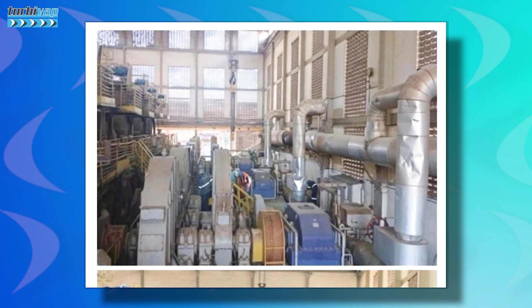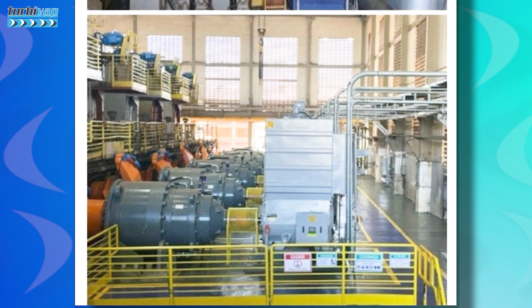Although robust and being improved to optimize their efficiencies, turbines face increasing challenges, such as stricter environmental regulations, carbon taxes, increased operating costs, and the need for greater availability and efficiency. When these machines age or no longer meet modern demands, replacing them with electrical systems appears as a strategic solution. Why this pressure for change? First, emissions. A simple gas turbine emits about half a kilo of CO2 per kilowatt hour, which for an 8 megawatt compressor operating 8,000 hours per year results in 32,000 tons of CO2 annually.